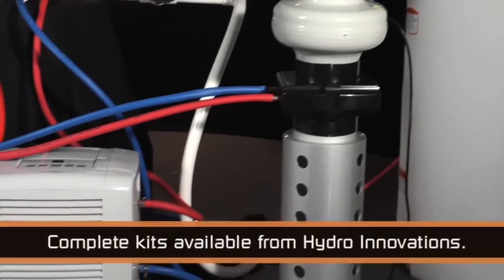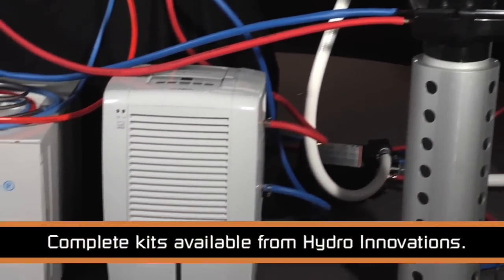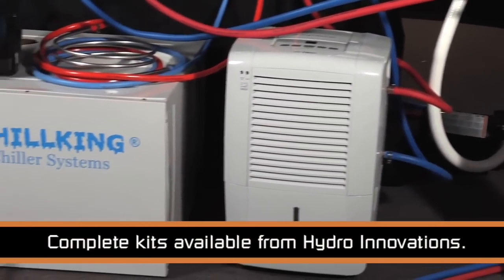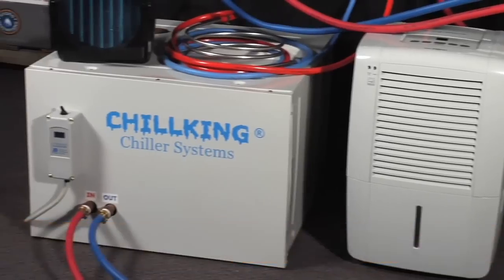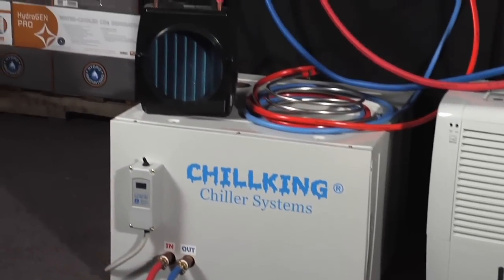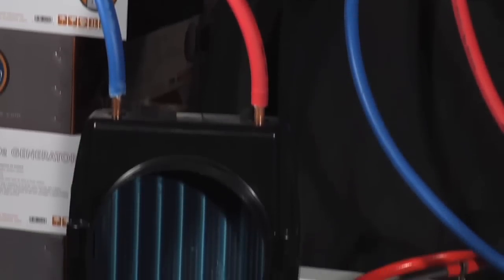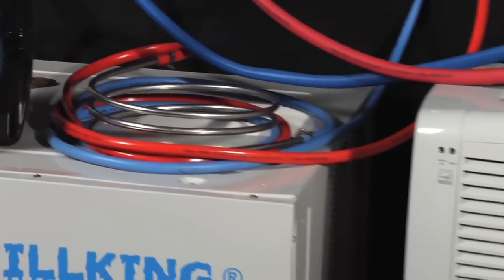The way we have this equipment set up here is strictly for demonstration purposes only. The chiller should absolutely go outside. All of the heat pulled out of your water-cooled equipment comes out of the back of this chiller, and it's inefficient to put it indoors. It must go outdoors to get rid of the heat efficiently.